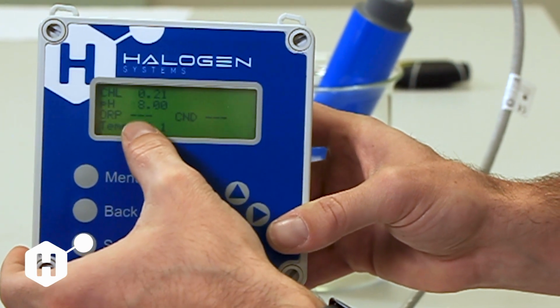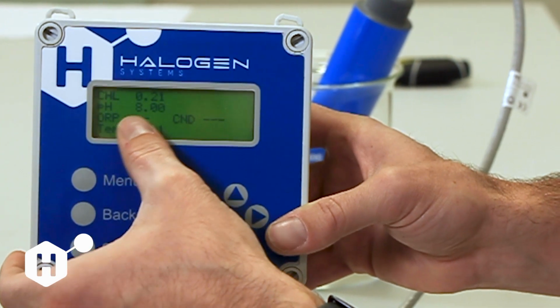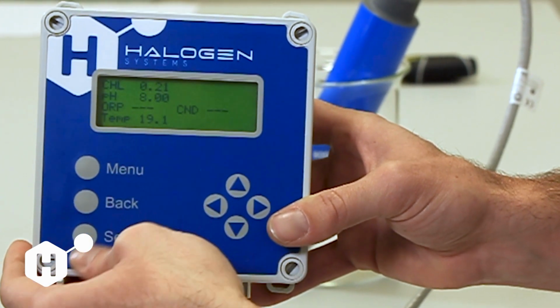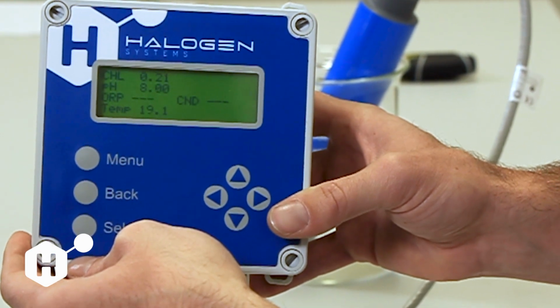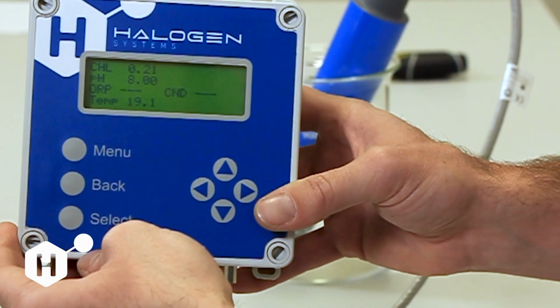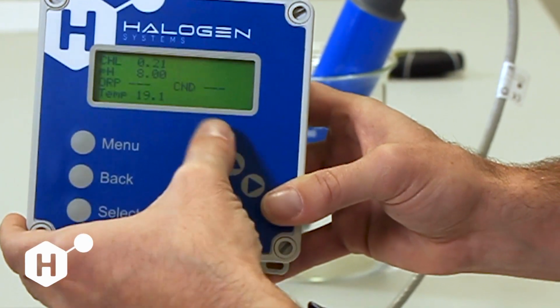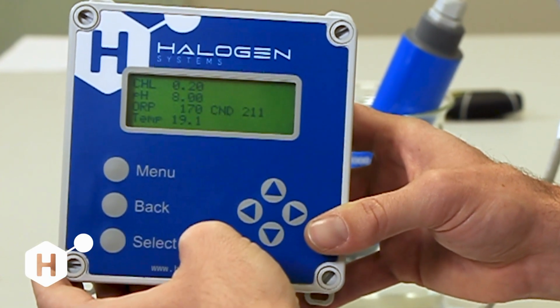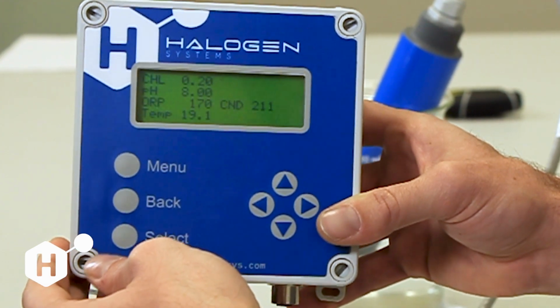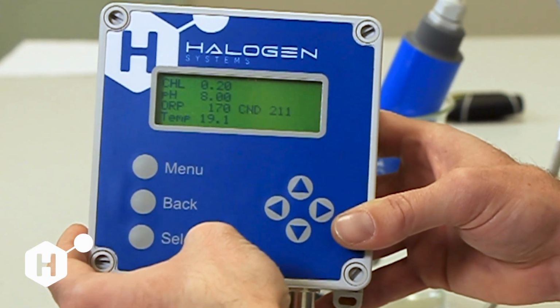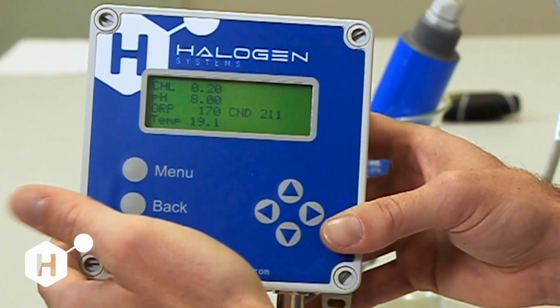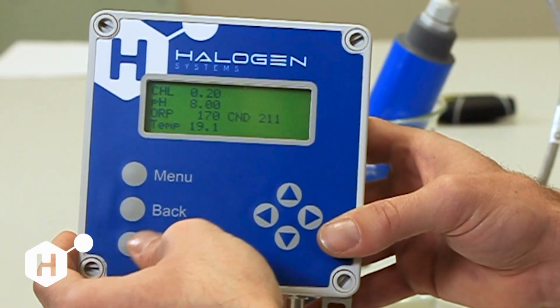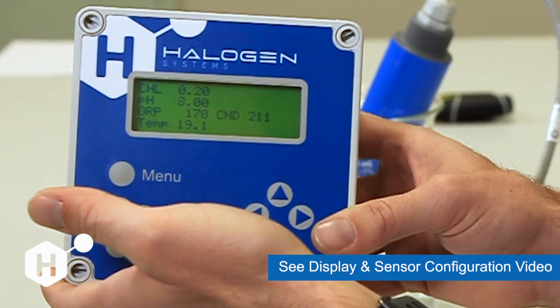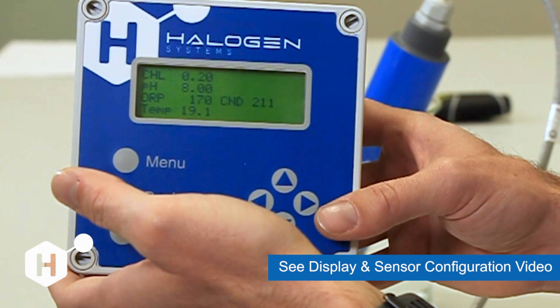It's going to take about a total of 1 minute and 45 seconds to get all 5 measurement parameters here. The first ones that are going to pop up are chlorine, pH, and temperature. ORP and conductivity will follow about 45 seconds later. Do not be alarmed, it is working normally, and we will get all of our measurements. And now you'll see that we have all of our measurements here. So the sensor looks like it's operating normally. The chlorine at 0.2 is about what I expected. I'm just running in tap water with a pH of 8. So my measurements here are looking about right. This is a good time to start configuring your 4 to 20 for your PLC as well. But at this point, I would say that this sensor has passed my commissioning test.